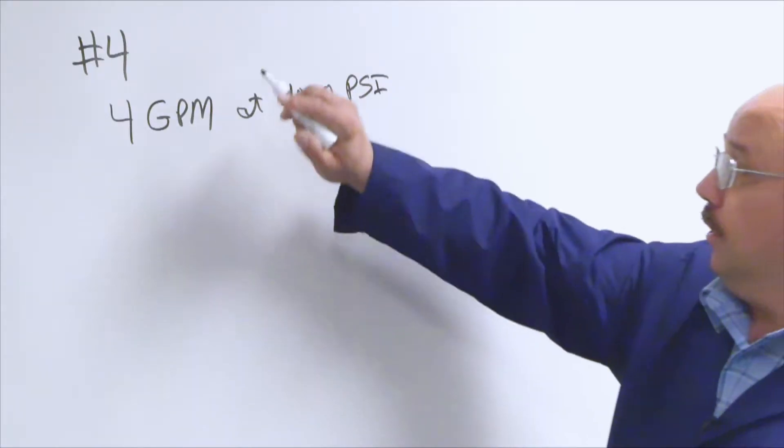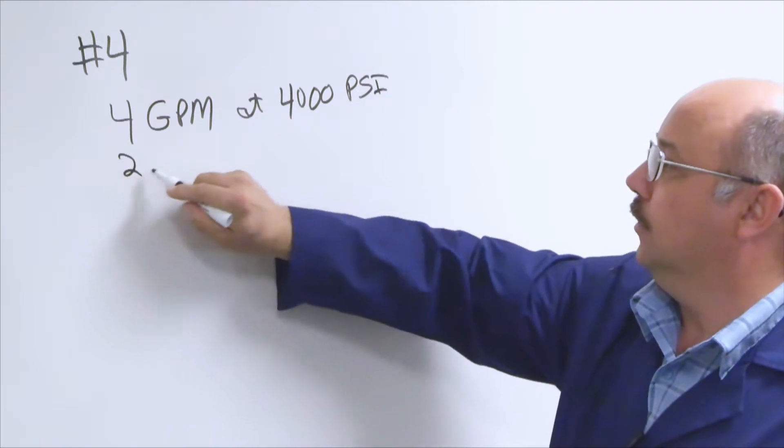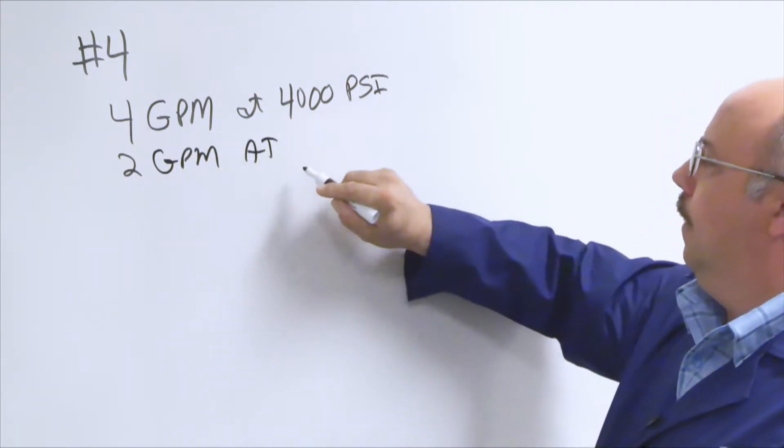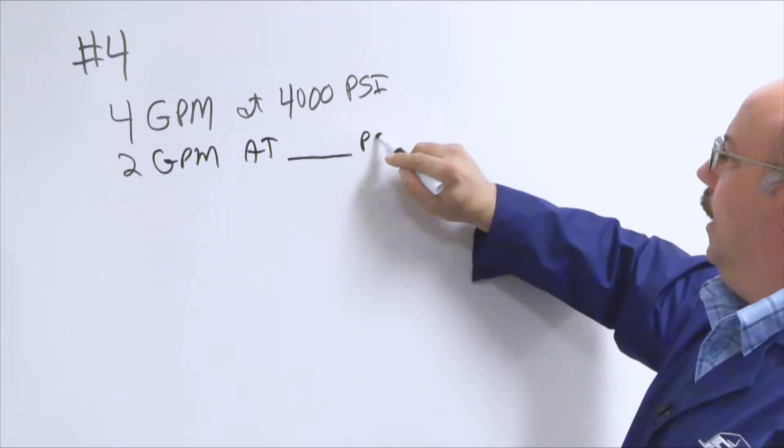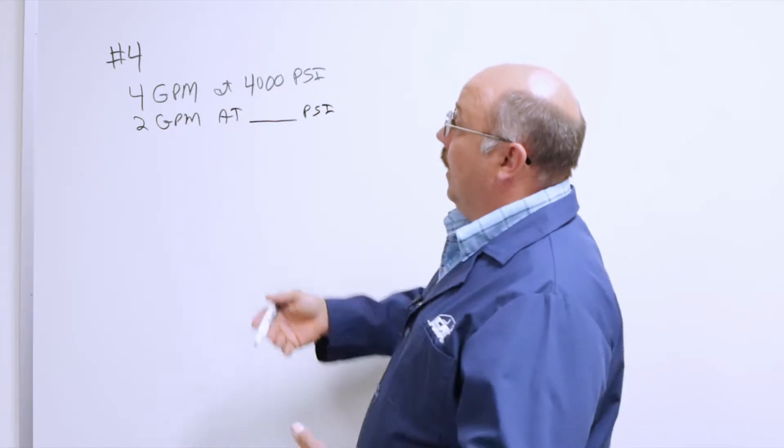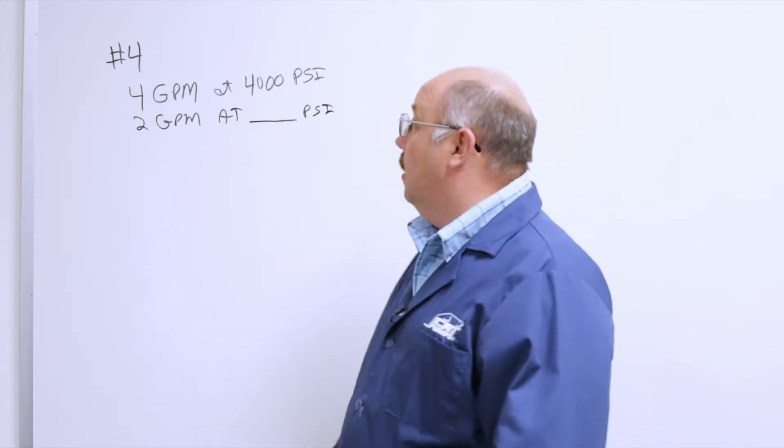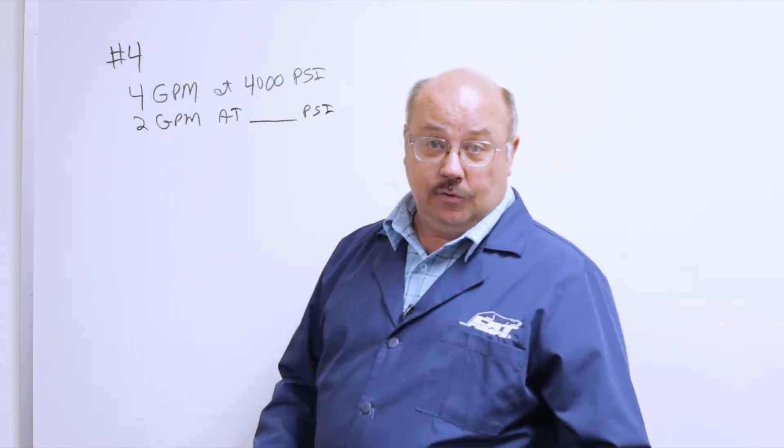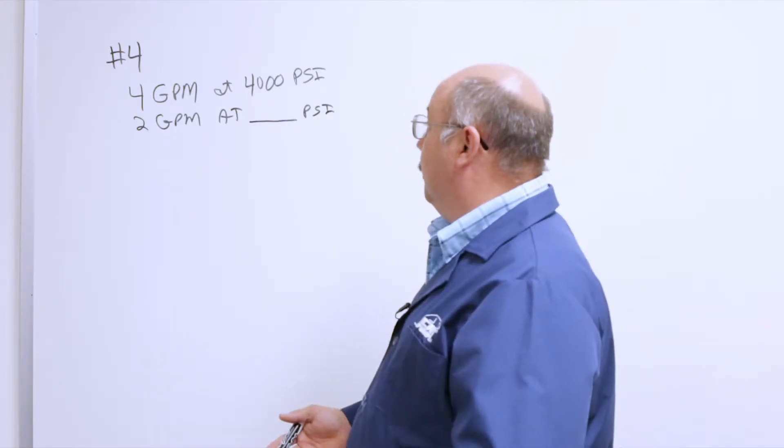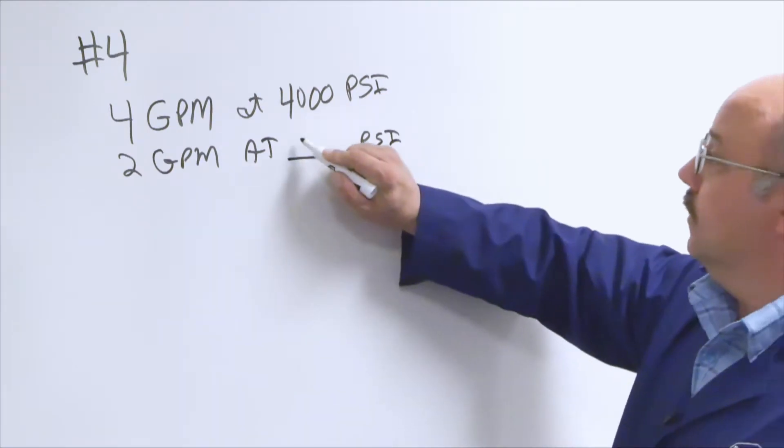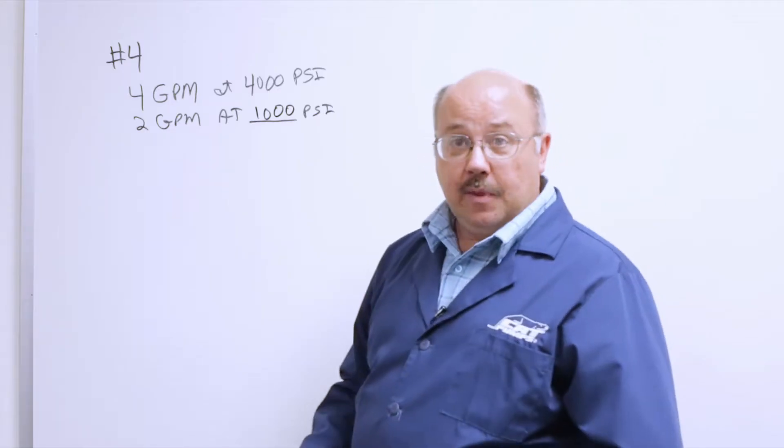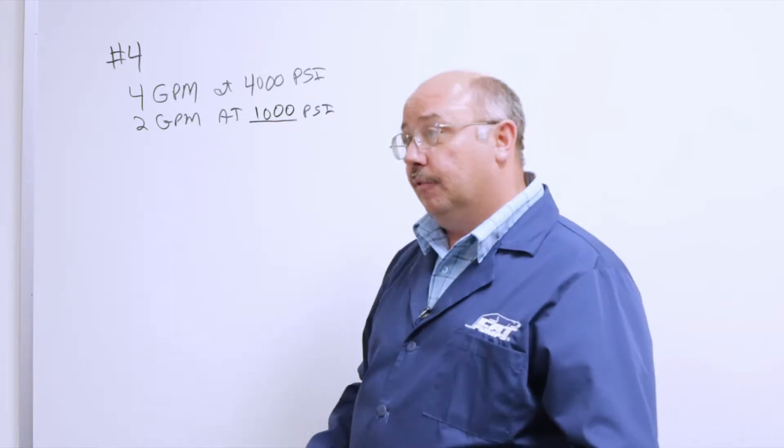So if I were to drop the flow on a number four nozzle to two GPM, what pressure would we have? One wants to think that it would be 2,000 psi because we got half the flow. But that actually is not true because it's a squared function the way the water goes through the nozzle and has a pressure drop. So the right answer is 1,000 psi.